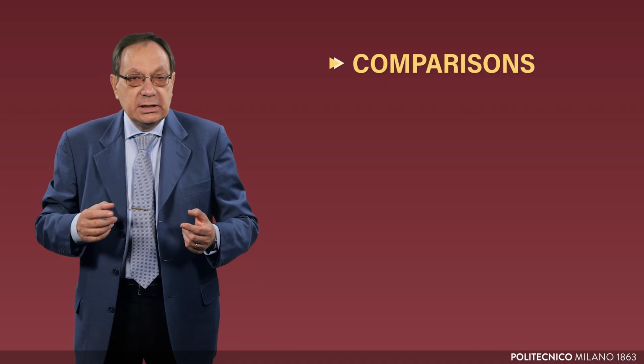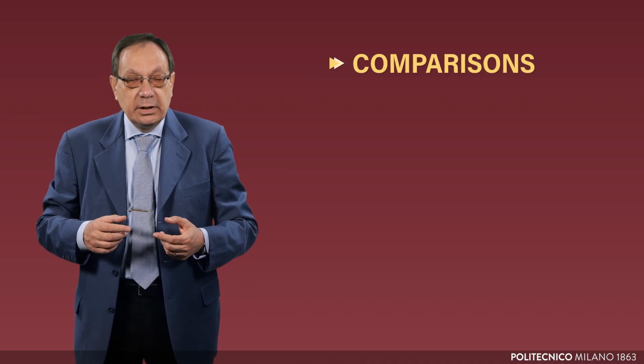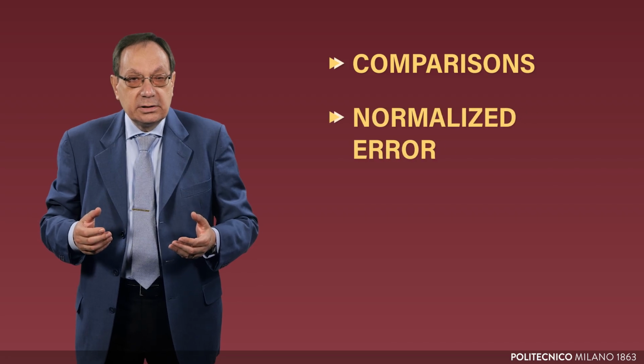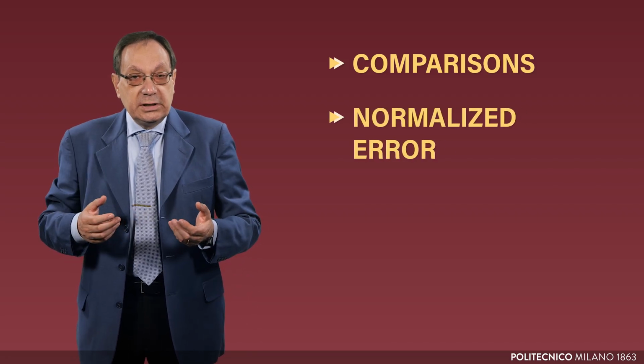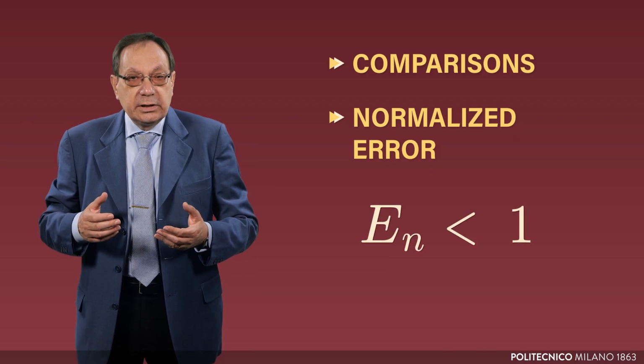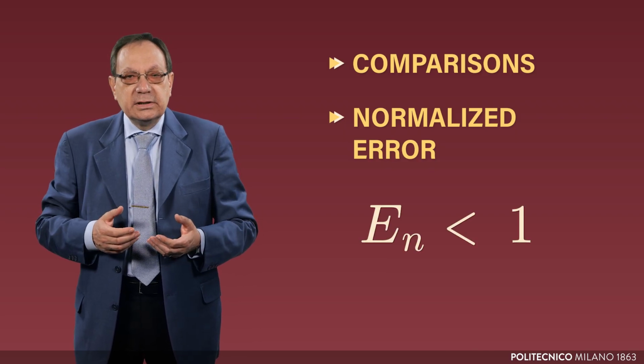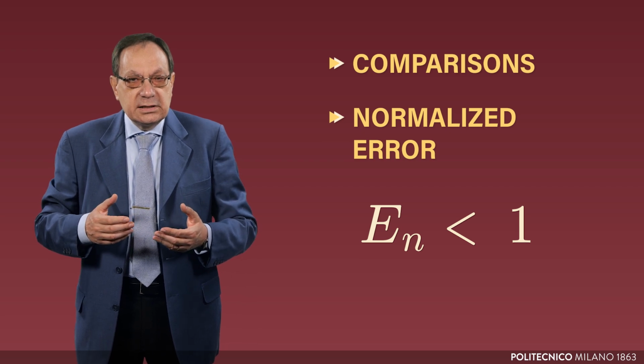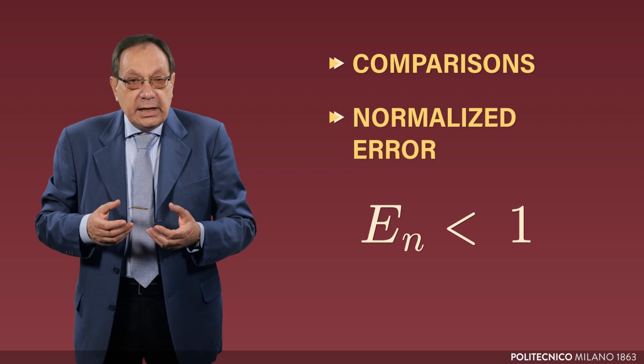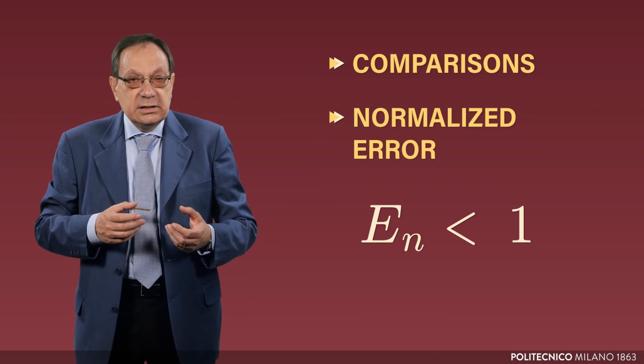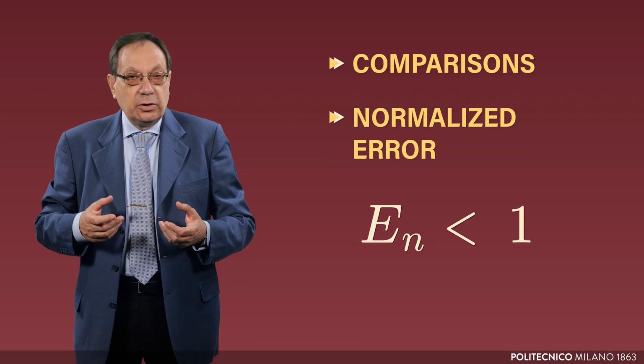It is in any case advisable to act before a situation arises in which the instrument, due to some internal drift, no longer meets the metrological requirements demanded by its intended use. In cases where it is possible to make comparisons between different instruments, as in the earlier example, it is sufficient to use the normalized error discussed in one of the previous lessons to assess metrological compatibility. A threshold lower than 1 is set, for example 0.75. If the instrument exceeds this value, it is then calibrated. In this way, action is taken before the characteristics of the instrument no longer meet the required metrological standards.